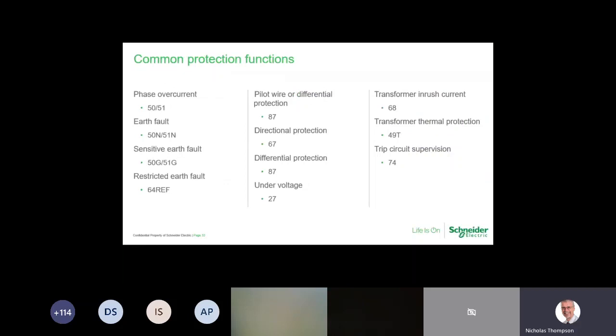So here are some of the common ones. So we've got 50 and 51, which I've covered earlier. Now we've combined a letter with a number. This is earth fault, so we've got N, which is earth fault in high voltage terms, or if you go into the definition within the ANSI code, it actually says neutral.